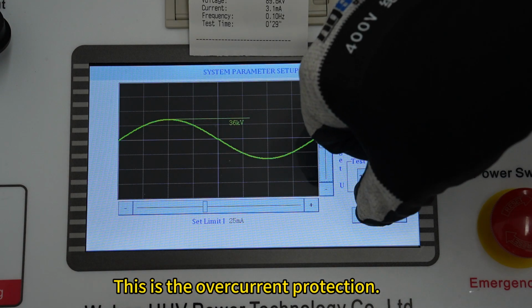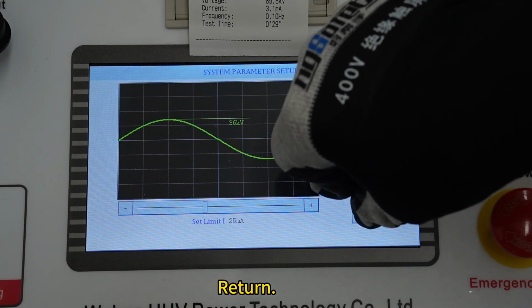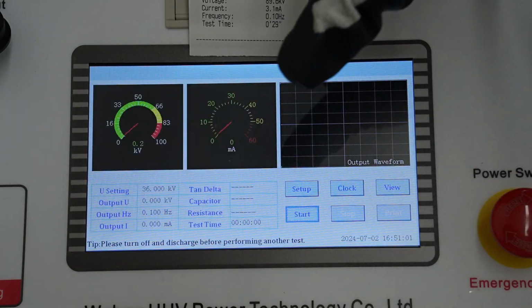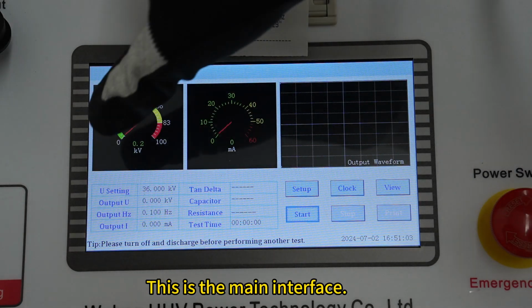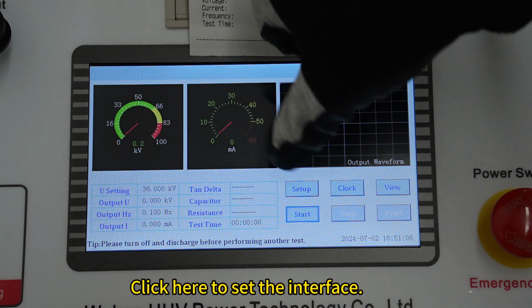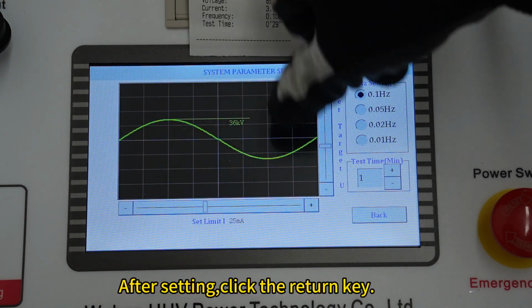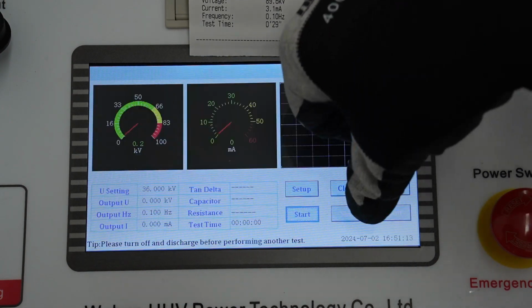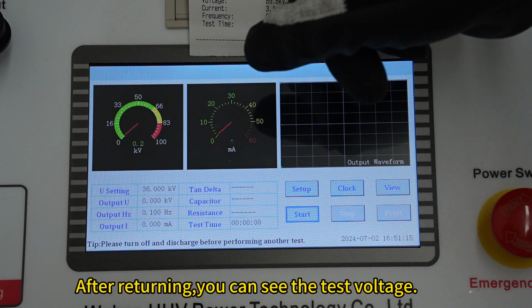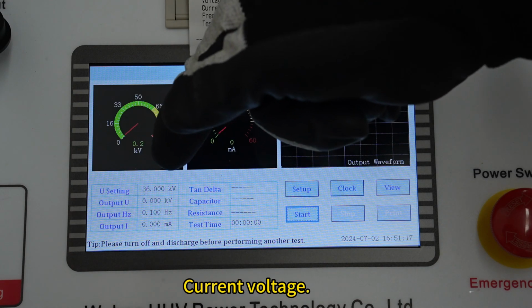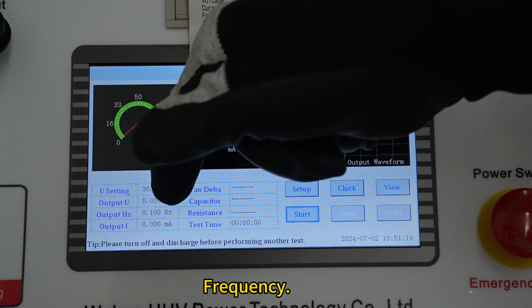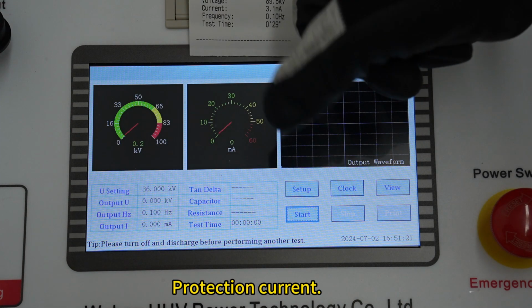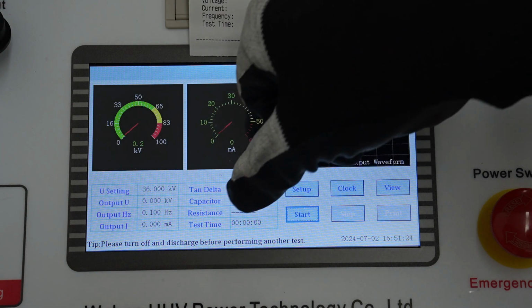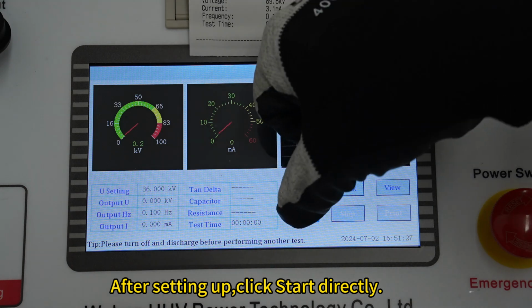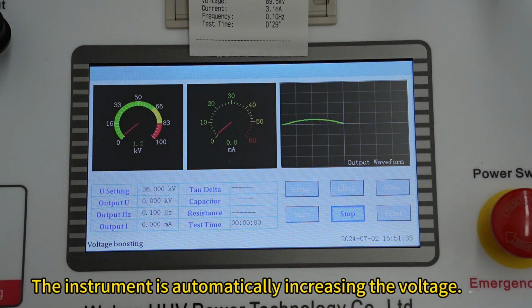This is the overcurrent protection. Return. This is the main interface. Click here to set the interface. After setting, click the return key. After returning, you can see the test voltage, current voltage, frequency, protection current, time. After setting up, click Start directly. The instrument is automatically increasing the voltage.